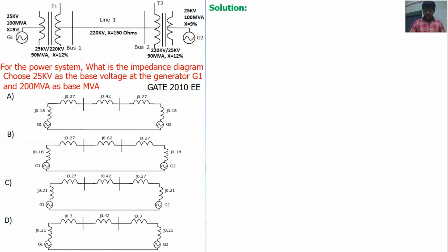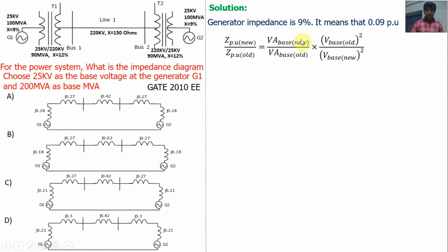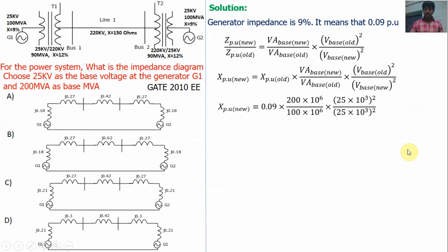First, we calculate the generator per unit impedance. The generator impedance is given as 9%, which means 0.09 per unit. This value applies when the base is 25 kV and 100 MVA. But the system base is different — 200 MVA — so we use the base-change formula: Z_pu_new equals Z_pu_old times (VA base new / VA base old) times (V base old squared / V base new squared). Substituting Z_pu_old = 0.09, VA base old = 100 MVA, VA base new = 200 MVA, V base old = V base new = 25 kV, the answer is 0.18 per unit.